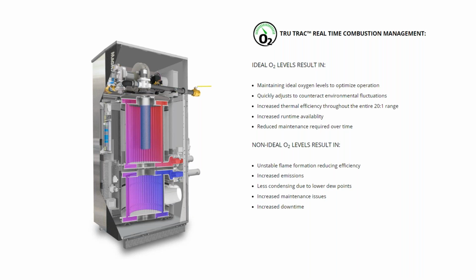So during the turn down, if we're not trimming everything together, you're going to have fluctuating flame rates. You're going to have increased emissions, less condensing due to lower dew points, because if we lose control of that oxygen, the temperature drops on the dew point. So we need to maintain that as well, and increase maintenance issues, which would be downtime. So O2 track is the way to go.